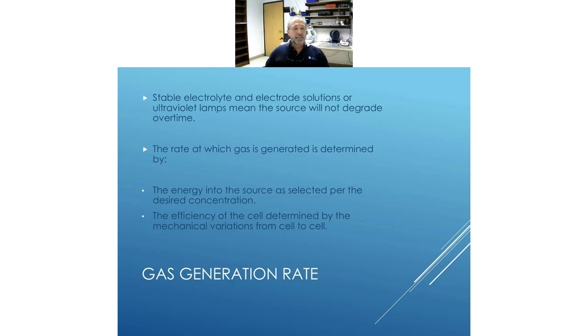Now the gas generation rate, again, we're talking about the electrochemical ones, the stable electrolyte. We can put a generating source together, put the liquid in it, and leave it for years, and nothing happens to it. Same with an ultraviolet lamp until we start to use it. So it doesn't sit on the shelf and degrade and go bad.